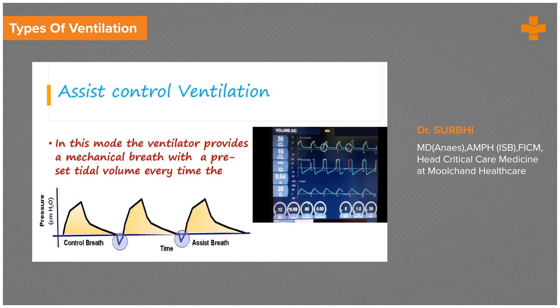In Assist Control Ventilation, unlike Controlled Mandatory Ventilation where even if the patient tried to trigger a breath the ventilator would not recognize it, in Assist Control when the patient tries to start a breath the ventilator recognizes it immediately and then delivers the breath totally as per either the set tidal volume or the set pressure. The patient can start the breath, the ventilator will recognize it, but after that the patient is totally supported by the ventilator — so patient comfort is greater.